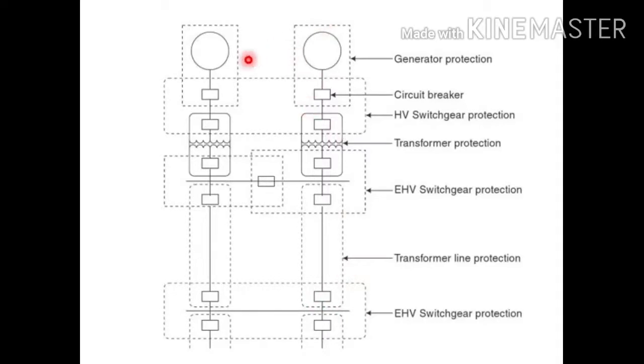Now with this we have a similar line on the left side. Now these circuit breakers are adjacent to each other. At the same time the generator protections are also adjacent to each other. So what is happening is that if any fault takes place over here, these four circuit breakers are going to trip, making sure that both the generator protections are safe.